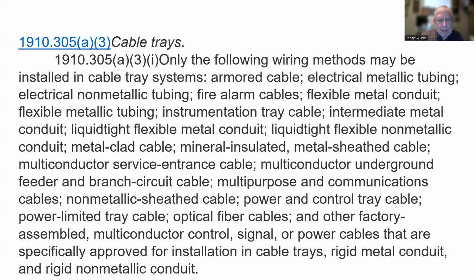Cable trays. Only the following wiring methods may be installed in cable tray systems: armored cable, electrical metallic tubing, electrical nonmetallic tubing, fire alarm cables, flexible metal conduit, flexible metallic tubing, instrumentation tray cable, intermediate metal conduit, liquidtight flexible metal conduit, liquidtight flexible nonmetallic conduit, metal clad cable, mineral insulated metal sheath cable, multiconductor service entrance cable, multiconductor underground feeder and branch circuit cable, multipurpose and communications cables, nonmetallic sheathed cable, power and control tray cable, power limited tray cable, optical fiber cables, and other factory assembled multiconductor control, signal or power cables that are specifically approved for installation in cable trays, rigid metal conduit, and rigid nonmetallic conduit. That's what is allowed. That's a lot. I don't know what else would not be allowed.